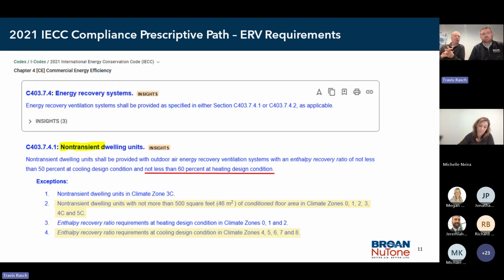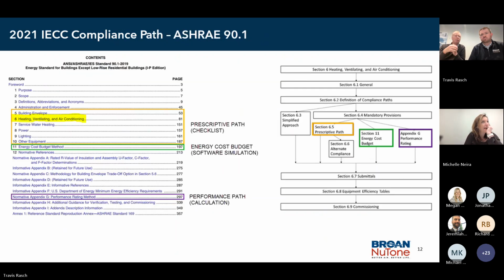We're focused on non-transient. So the key here, when you go the ERV path, is as underlined in red there, you need to be not less than 60% at heating design conditions. If you look below, it's all based on climate zone. Since Pennsylvania is only climate zone 4 and 5, we don't need to worry about cooling design conditions, we're focused on heating only, which simplifies things a little bit - you only have to worry about one of the two requirements you have to hit.